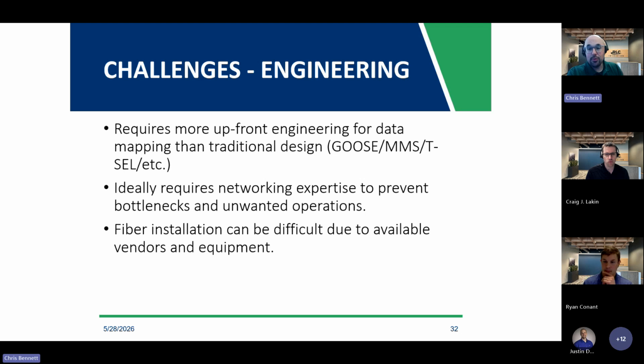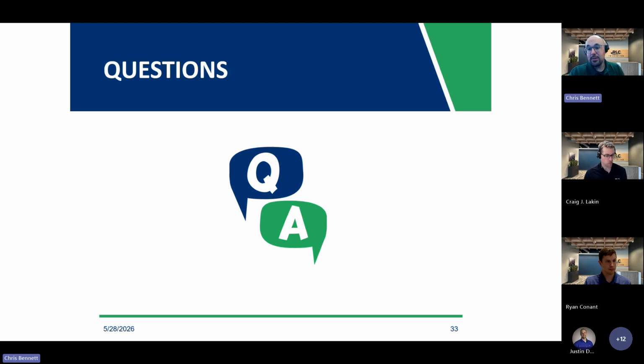Traditionally, those are two completely separate worlds, and now they're being merged together, which could create some challenges as to what's compatible, what's best, what speeds do I need, what bandwidth. It becomes a challenge for roping in more folks than ever before. And finally, one of the not so obvious downsides is that fibers and fiber installation is usually finicky and difficult. Depending on your available vendor, what types of fibers you want, and what equipment you're using, it can be long lead and it can be difficult to install and procure. So, yeah, those are some of the highlights to the challenges.